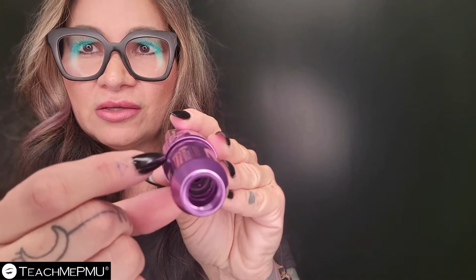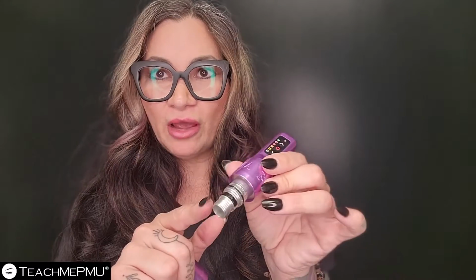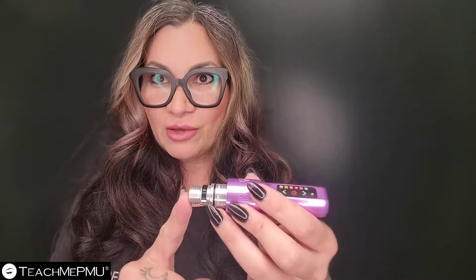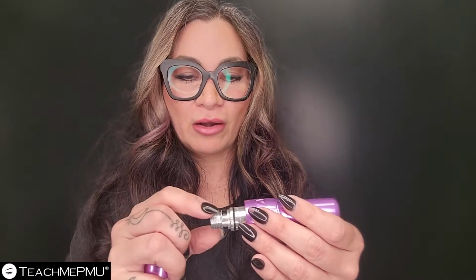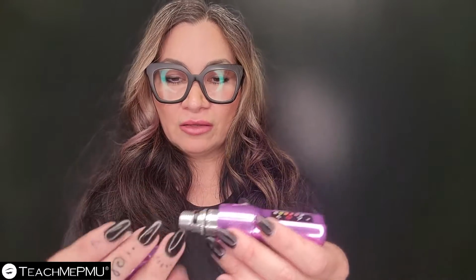Now, I don't recommend using these without covering the whole machine because you still have, look at in here, there's this whole lip right here. And then also, this is part of the machine, so you're not able to autoclave this. So you definitely don't want to not use a barrier product with these machines because body fluids, bloodborne pathogens, bacteria, anything can get up inside here, and then you're not really able to properly autoclave it. However, if you have barrier film all around it and it becomes compromised, you can absolutely wipe it down with cold sterilization, and you could take the grip off and throw it in the autoclave.